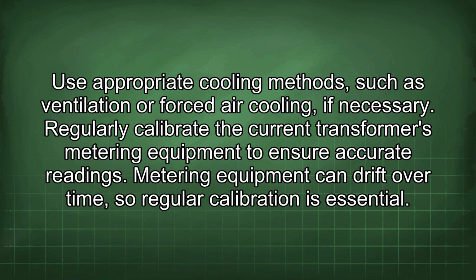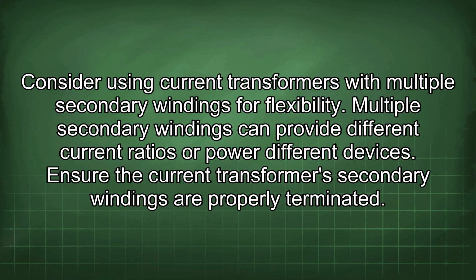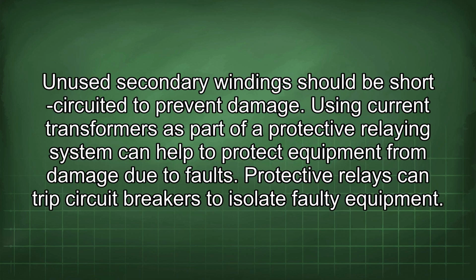Regularly calibrate the current transformer's metering equipment to ensure accurate readings. Metering equipment can drift over time, so regular calibration is essential. Consider using current transformers with multiple secondary windings for flexibility. Multiple secondary windings can provide different current ratios or power different devices. Ensure the current transformer secondary windings are properly terminated. Unused secondary windings should be short-circuited to prevent damage.